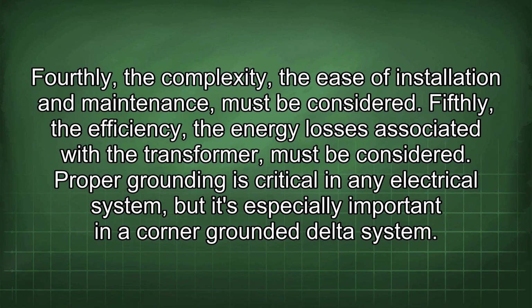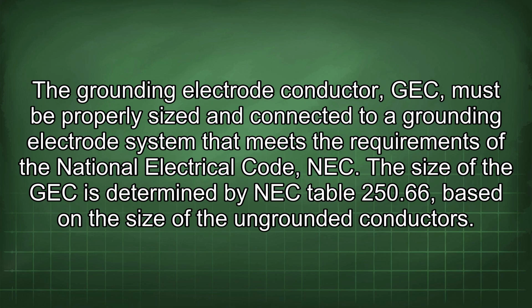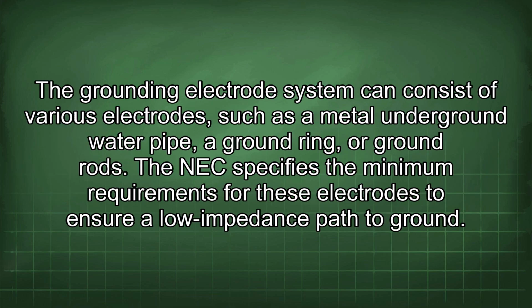Proper grounding is critical in any electrical system, but is especially important in a corner grounded delta system. The grounding electrode conductor, GEC, must be properly sized and connected to a grounding electrode system that meets the requirements of the National Electrical Code, NEC. The size of the GEC is determined by NEC Table 250.66 based on the size of the ungrounded conductors. The grounding electrode system can consist of various electrodes, such as a metal underground water pipe, a ground ring, or ground rods. The NEC specifies the minimum requirements for these electrodes to ensure a low impedance path to ground.